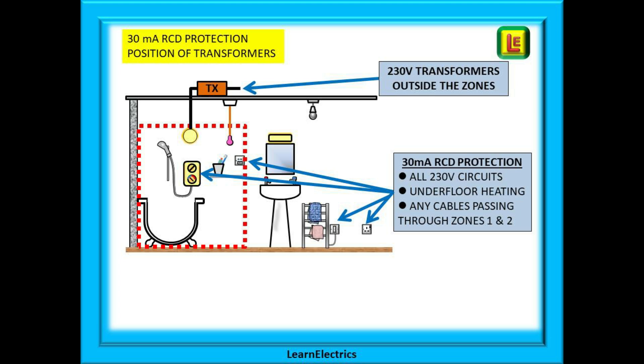Regarding RCD protection: all 230 volt circuits in a bathroom or room with a shower must be 30 milliamp RCD protected. Underfloor heating should also have 30 milliamp RCD protection, and any cables that pass through the bathroom or room with a shower that are in Zones 1 or 2 but are not used in those rooms must also be 30 milliamp RCD protected. Where SELV or PELV is in use, the 230 volt transformer that supplies the extra low voltage must be sited outside the zones, and only the cables at extra low voltage should be in the zones.